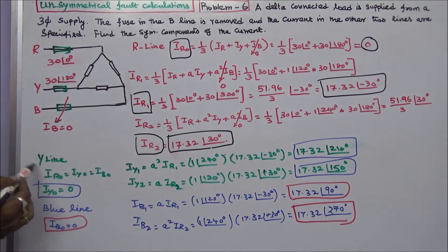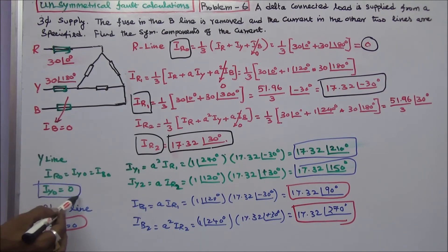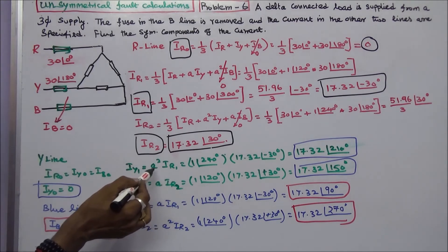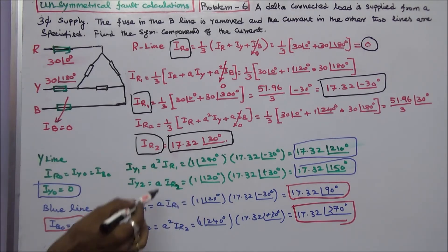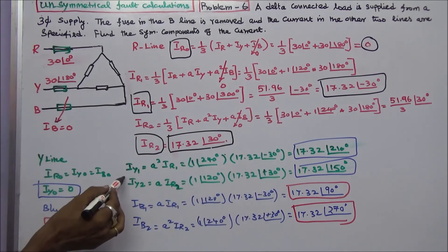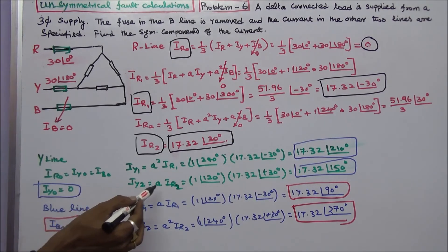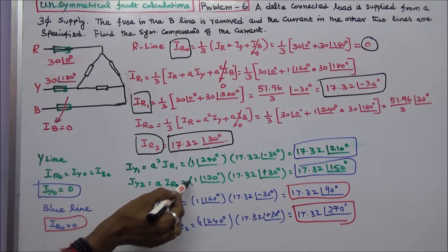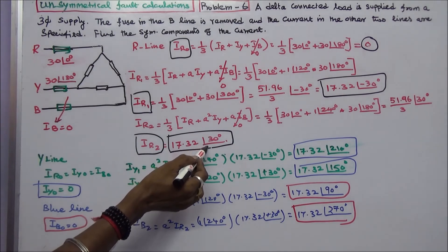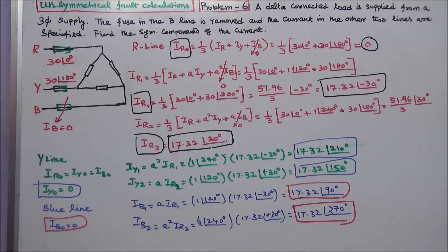Next, we consider the Y line. IY0 equals IR0 equals IB0, so IY0, the zero sequence current, is 0. The positive sequence current in the Y phase is IY1 equals A²·IR1. Here A² equals 1 angle 240 degrees and IR1 equals 17.32 angle minus 30 degrees, so IY1 equals 17.32 angle 210 degrees. IY2 equals A·IR2, where A is 1 angle 120 degrees and IR2 equals 17.32 angle 30 degrees, therefore IY2 equals 17.32 angle 150 degrees.